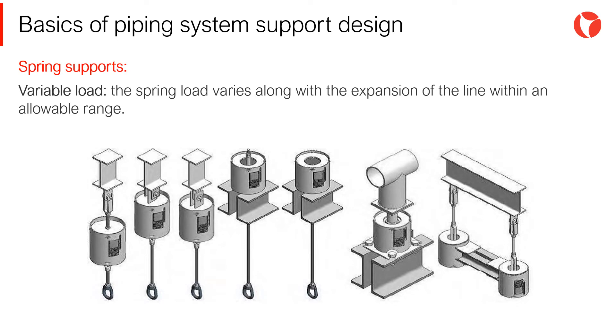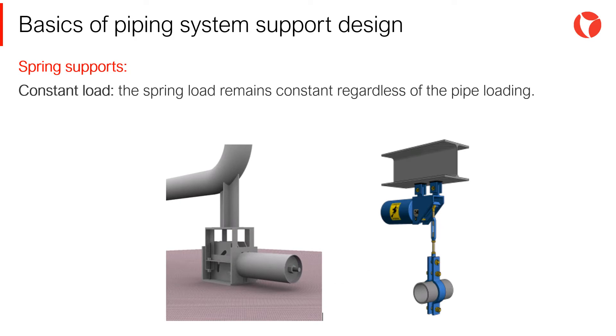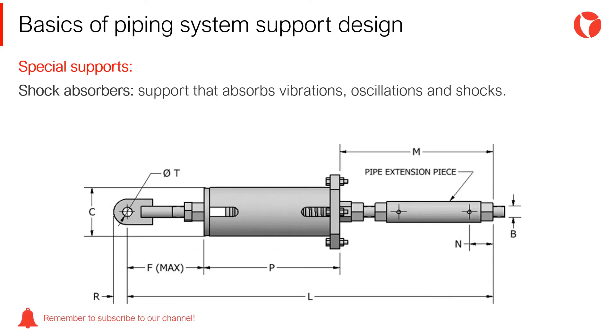Spring supports — variable load: within spring supports, variable load supports are the most used. The spring load varies along with the line expansion within an allowable range. In constant load spring supports, the load remains constant regardless of the loads in the pipe, due to a system of internal levers. Finally, within the special supports, we find shock absorbers — also known as hydraulic shock or sway suppressors — whose application is limited to the absorption of rapid movements such as vibrations, oscillations, and shock loads.